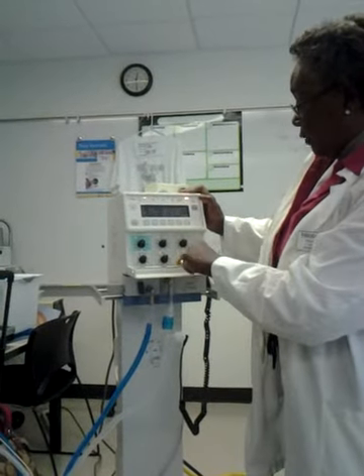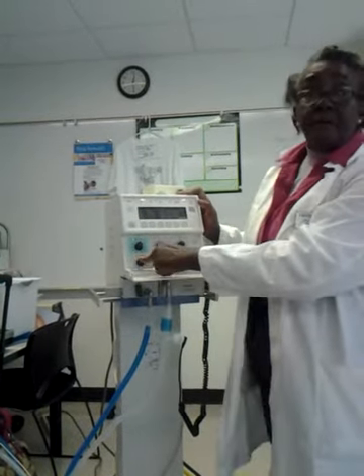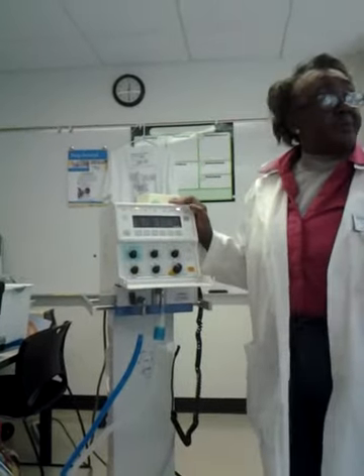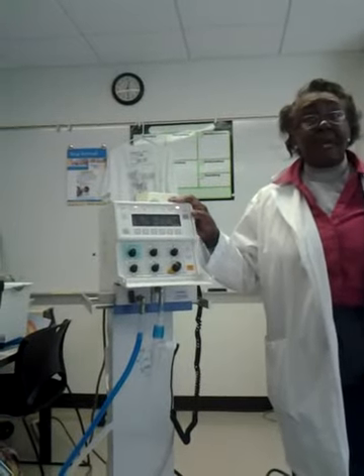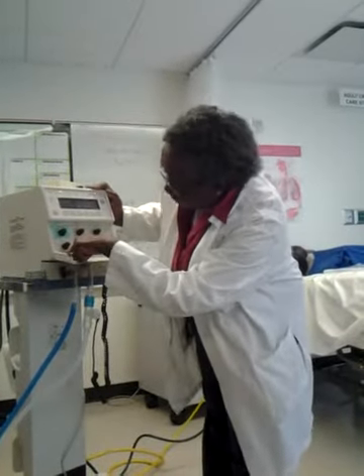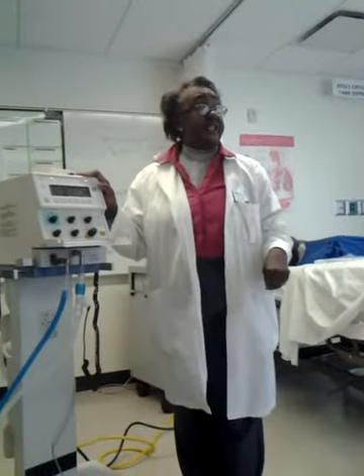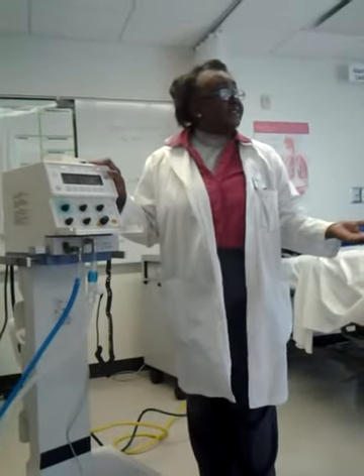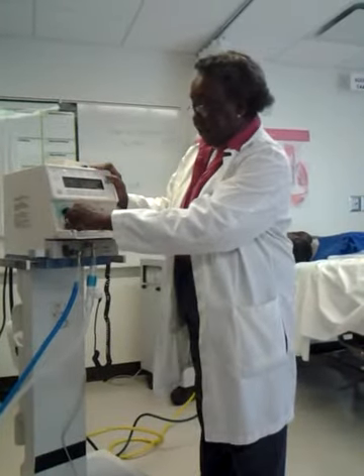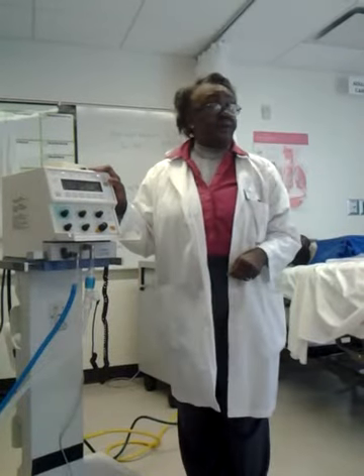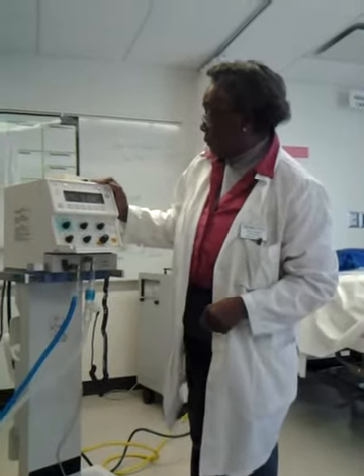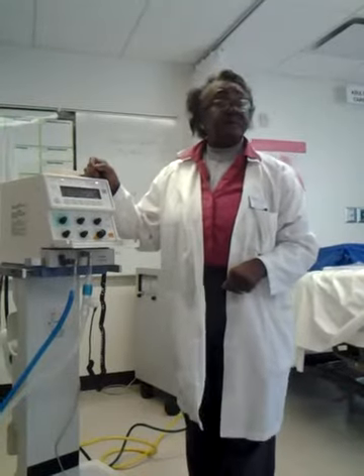The other thing that you can manipulate is your peak flow. How fast do you want that breath to go into the baby? Now keep in mind with your adults, we're using things like 40 to 60 liters per minute. If you look down here, it starts at 1 and it goes only up to 30 liters per minute. Depending on the size of your infant, 8, 10, 12 liters per minute is what you're going to be working with.